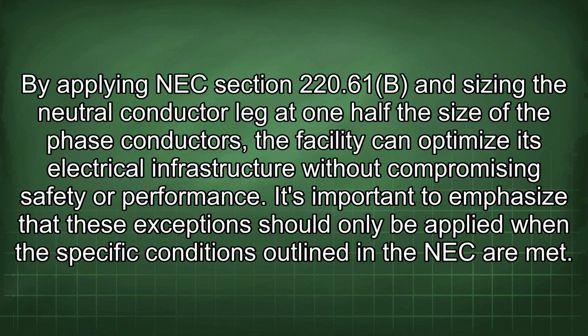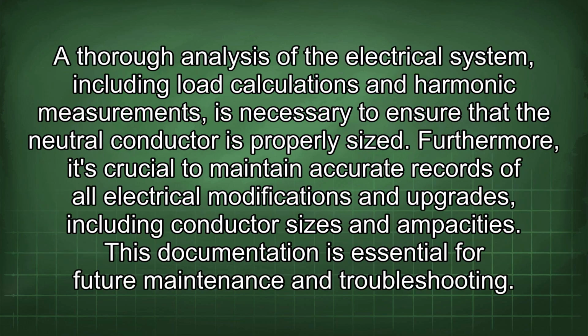It's important to emphasize that these exceptions should only be applied when the specific conditions outlined in the NEC are met. A thorough analysis of the electrical system, including load calculations and harmonic measurements, is necessary to ensure that the neutral conductor is properly sized. Furthermore, it's crucial to maintain accurate records of all electrical modifications and upgrades, including conductor sizes and ampacities. This documentation is essential for future maintenance and troubleshooting.